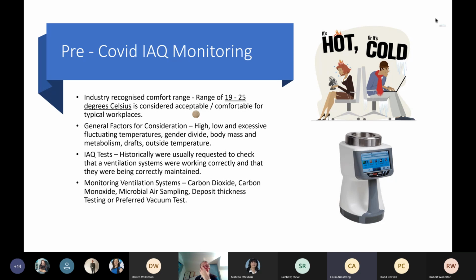The air sampling, though, if you do use it, there's a piece of equipment on the slide there, and you just put a blank plate in the top of it. Then you take samples from at least 2 rooms served by the air handling unit, and try and put one near the start of the AHU system, and one at the furthest. So you're getting a range of what that's going to be at either end. If you've got a high reading at the start and a high reading at the end, you know it's going to be the same way through. But if it's high at one and low at the other, you can then try and work it out.